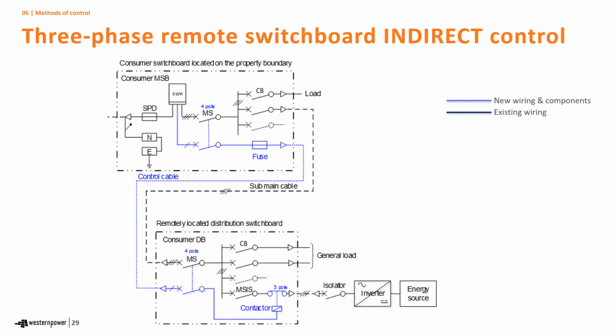Three-phase remote switchboard with indirect control. Again, this is where it is feasible to do this. As we mentioned earlier, there's a lot of places where this will not be feasible. As you can see, you still need a 4-pole main switch on the main switchboard. You'll need to add a 4-pole main switch on the subboard to comply with 3000 requirements.